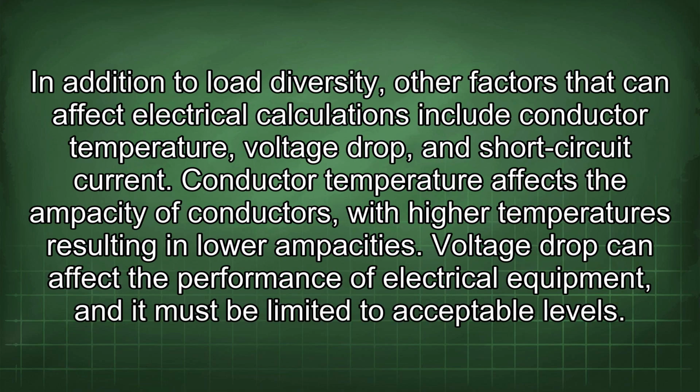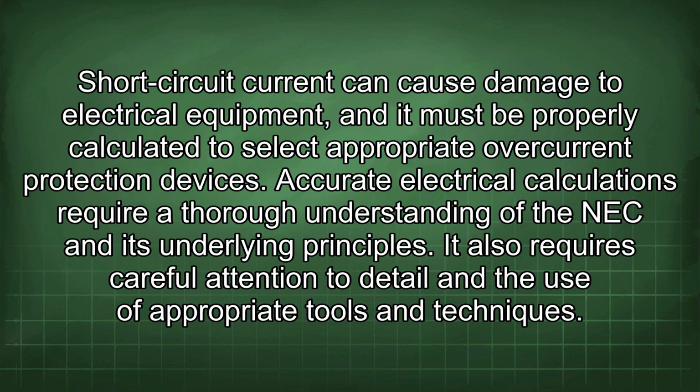In addition to load diversity, other factors that can affect electrical calculations include conductor temperature, voltage drop, and short-circuit current. Conductor temperature affects the ampacity of conductors, with higher temperatures resulting in lower ampacities. Voltage drop can affect the performance of electrical equipment, and it must be limited to acceptable levels. Short-circuit current can cause damage to electrical equipment, and it must be properly calculated to select appropriate overcurrent protection devices.